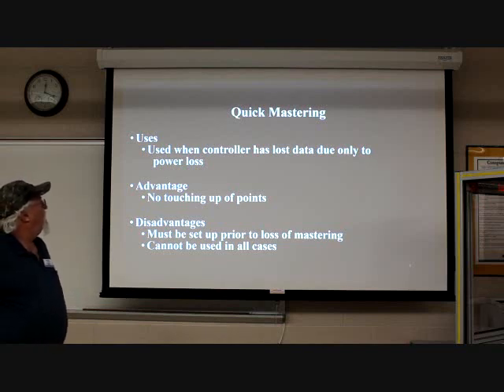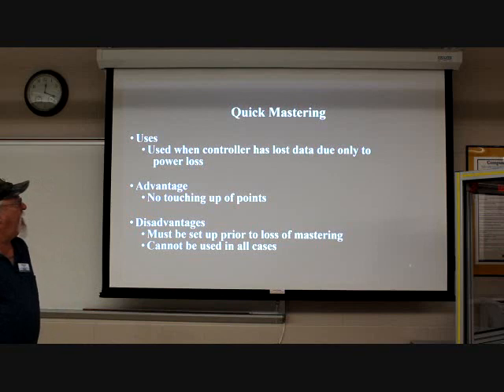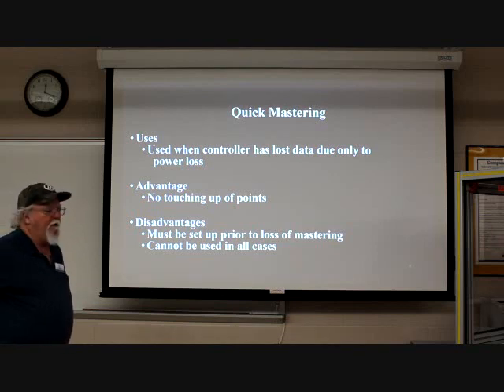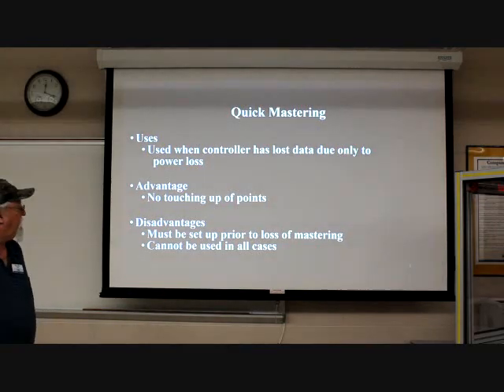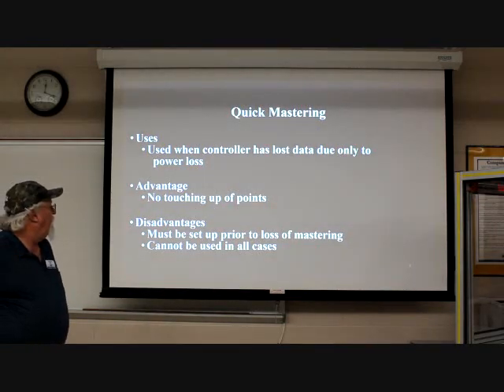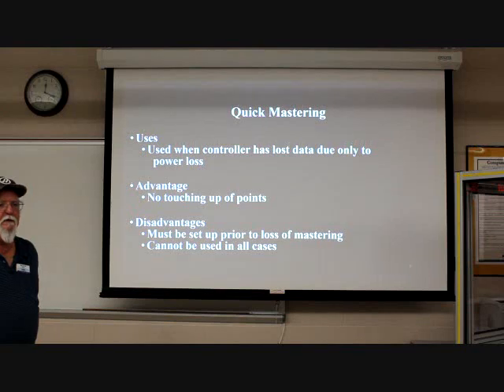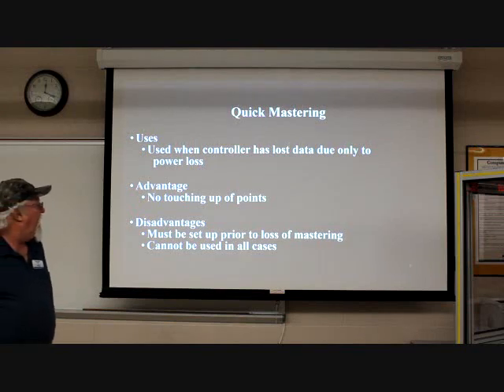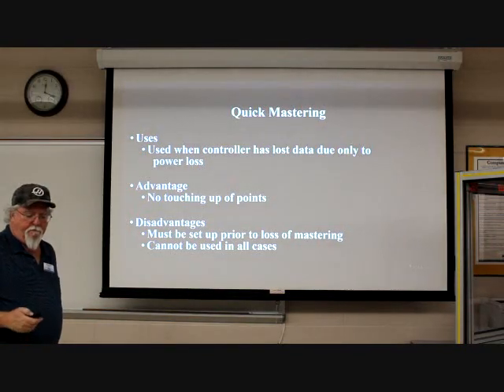Quick mastering we can use when the controller has lost data due to only power loss. The advantage, we don't have to touch up our points. Disadvantages, we must set this up prior to loss of mastering. And it cannot be used in all cases.